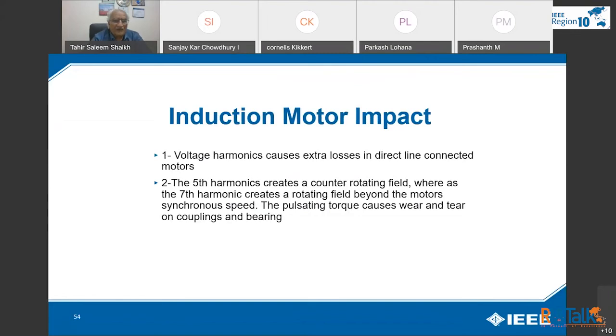A voltage harmonic causes extra losses in the direct line connected motor. And for VFD, the fifth harmonic creates a counter rotating field, whereas the seventh harmonic creates a rotating field beyond the motor's synchronous speed. The pulsating torque causes wear and tear on coupling and bearing. The general increased use of VFDs creates this type of fault for induction motors.